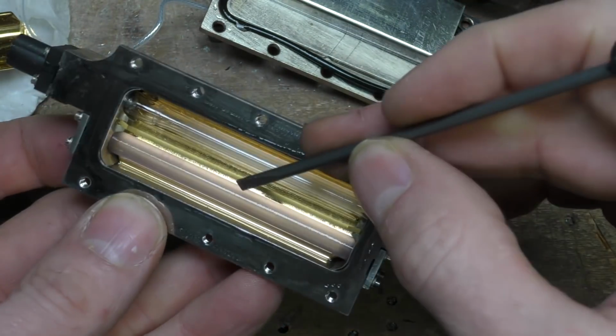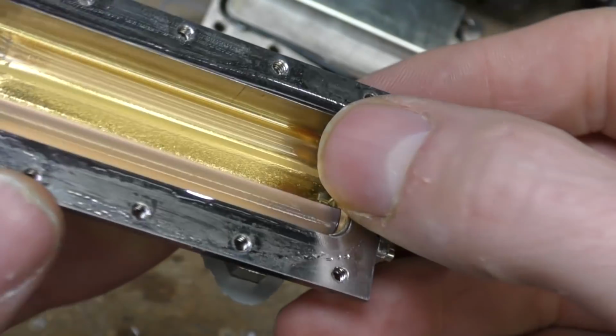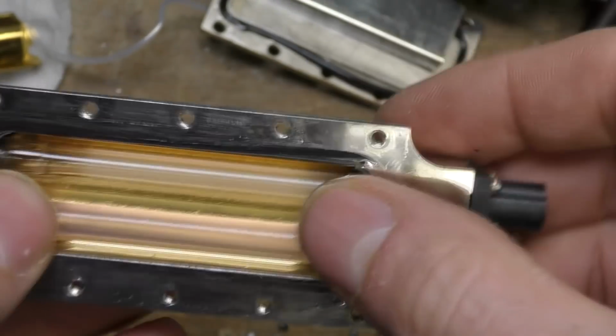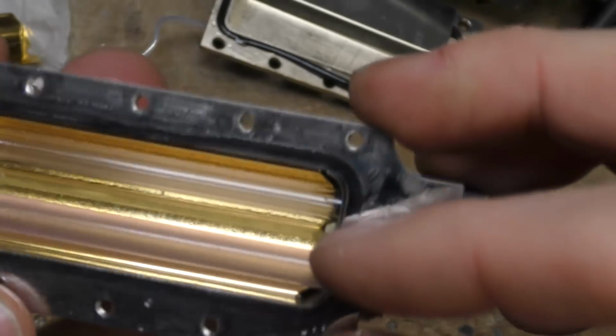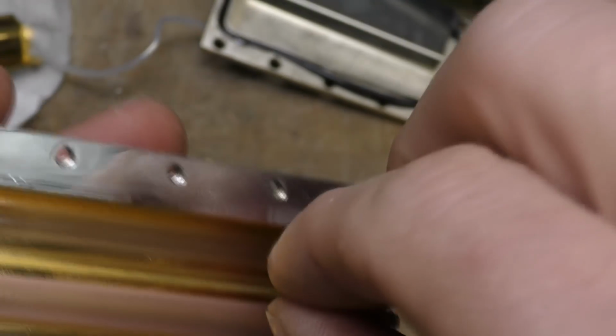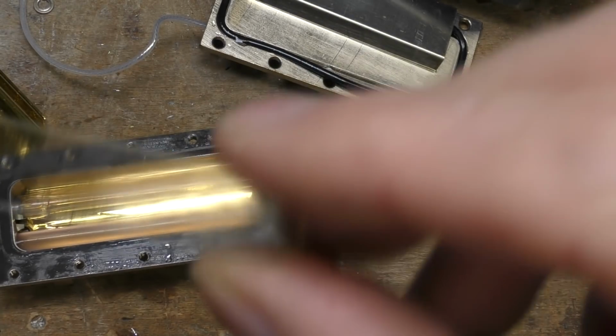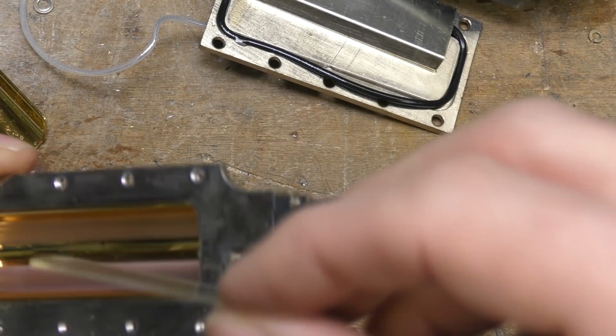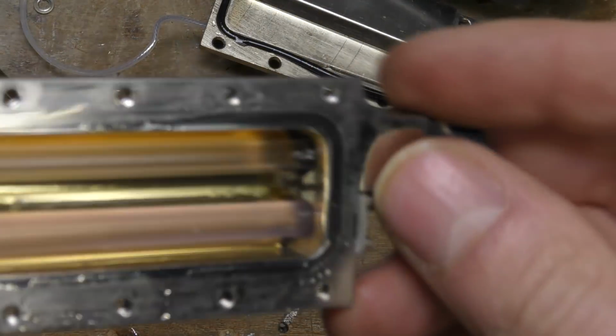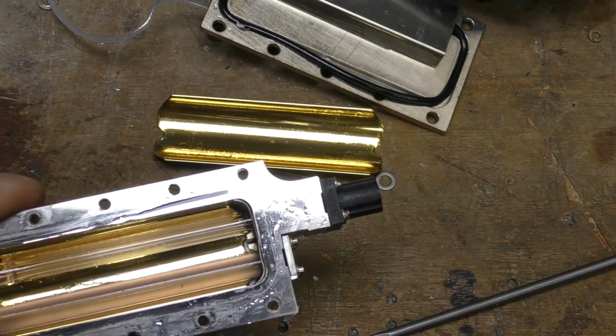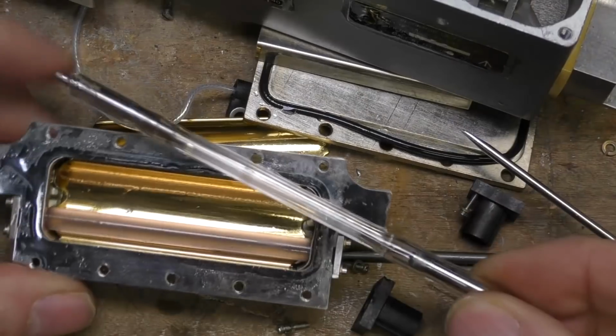There's a piece of glass, or the plastic or glass, between the tube and the YAG rod. It doesn't seem to be for sealing the coolant, because there's no seal on there. So I wonder if maybe this is doing some sort of optical filtering. Yeah, it's glass rather than plastic. I can't think what else that would be other than some filtering, perhaps filtering out the infrared or some group of wavelengths from the flash tube. And there's also a similar profile underneath, so it's focusing all the energy towards the rod from the flash tube.